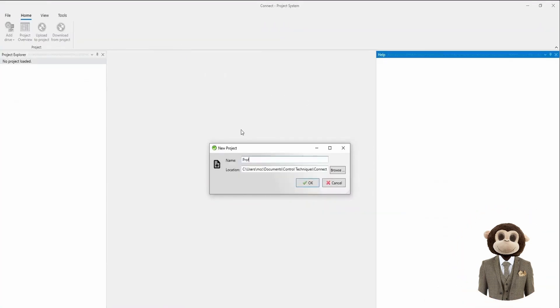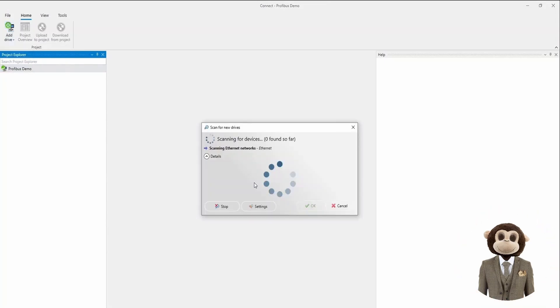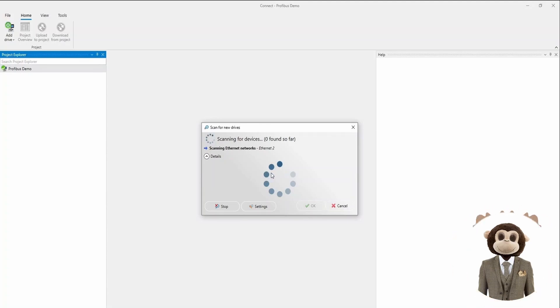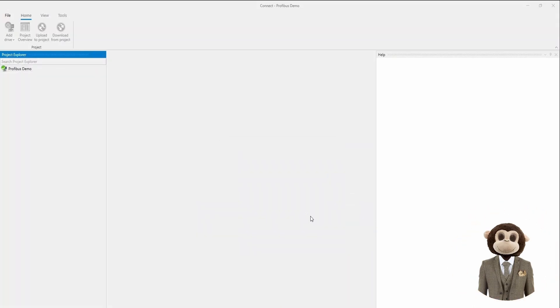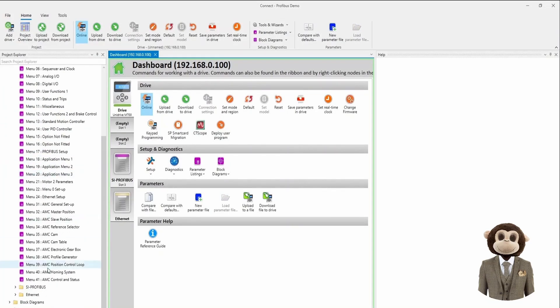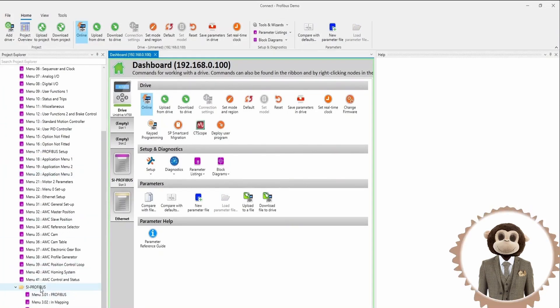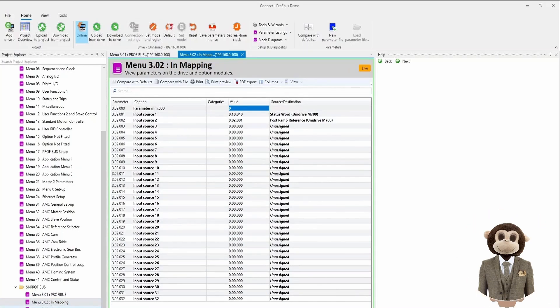We're going to create a new project. We already have a drive connected to the computer with the IP address set up — we're going to scan and add that drive. The motor data is already set up in the drive, so all we're going to show is the PROFIBUS module setup. In this case, this is an M700 with the SI PROFIBUS module installed in slot number three. We go to the PROFIBUS module and open up menus one, two, and three for the input and output mappings — these are the default values.